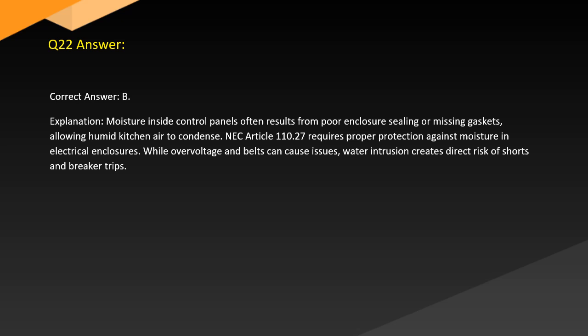Answer. Correct answer. B. Explanation. Moisture inside control panels often results from poor enclosure sealing or missing gaskets, allowing humid kitchen air to condense. NEC Article 110.27 requires proper protection against moisture in electrical enclosures. While overvoltage and belts can cause issues, water intrusion creates direct risk of shorts and breaker trips.